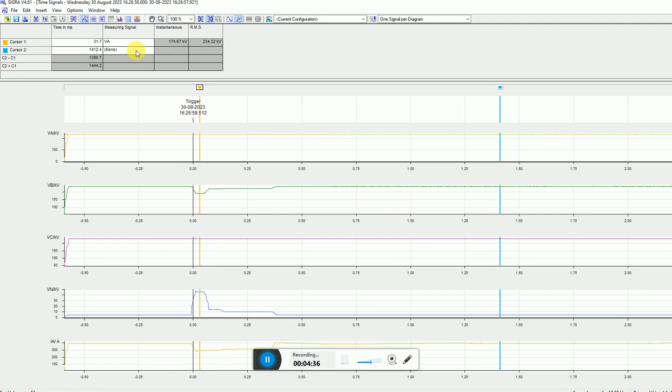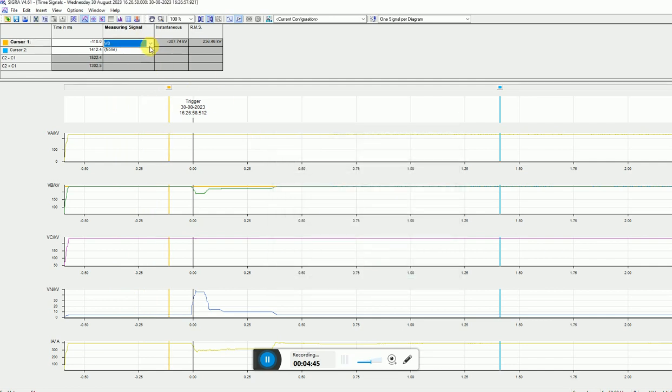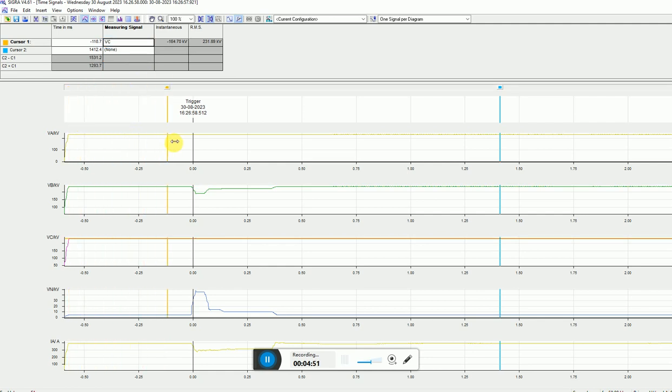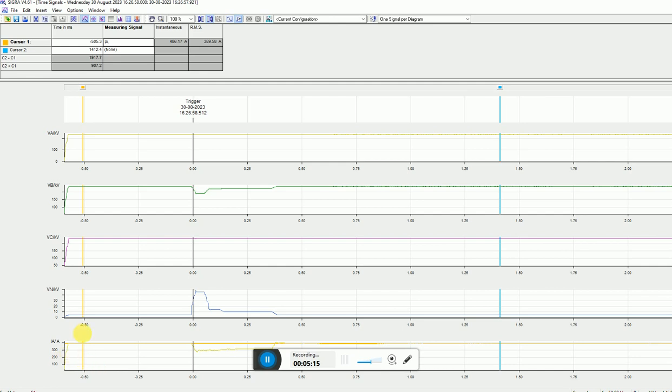Like that, you can select Y phase also. Y phase also 236. You can select for B phase also. Drag to B phase and you can see voltage is 231 kV. So all voltage is normal, that is 235 kV, and there is no tripping in the relay. We will see in the digital channel what happened. You can check current also. What is the value of current? Select the cursor IA and move the cursor on IA. Here you can see the current is 389.